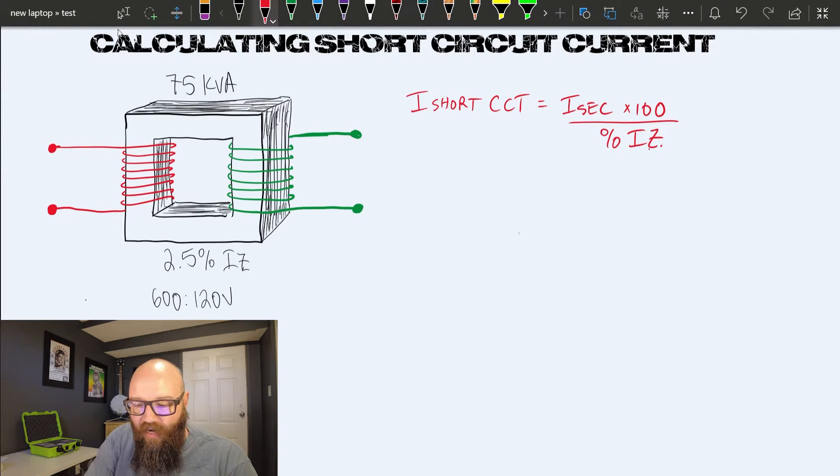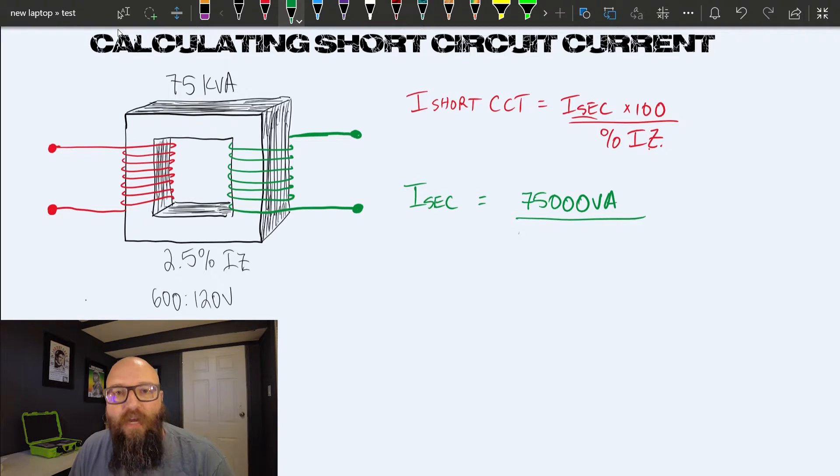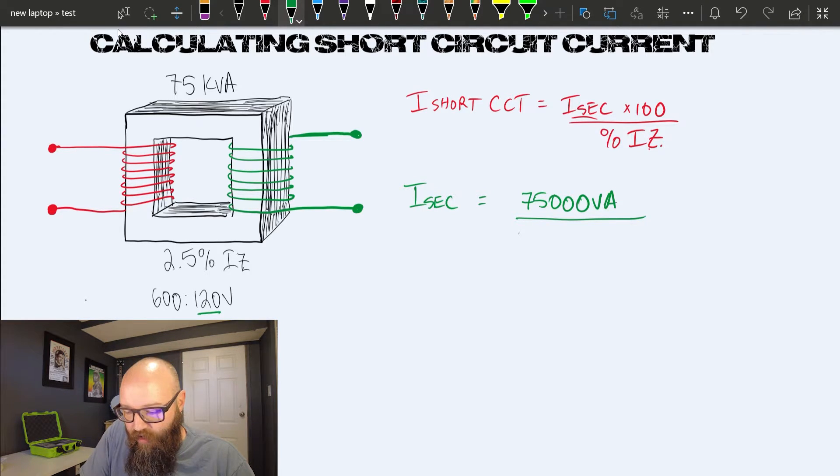Before we do that, I need to know my I secondary. I secondary in this case equals my VA rating of 75,000 VA divided by—in this case it's a single phase transformer, so I don't have to worry about using root three. I do need to grab that line voltage though. Our line voltage on the secondary is 120 volts. So 75,000 VA divided by 120 gives me a secondary rated current of approximately 625 amps.